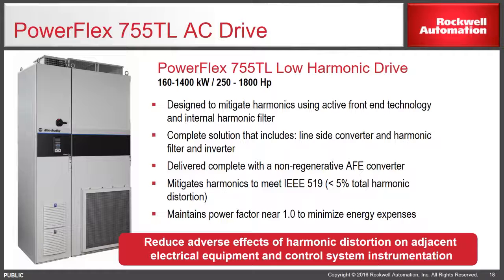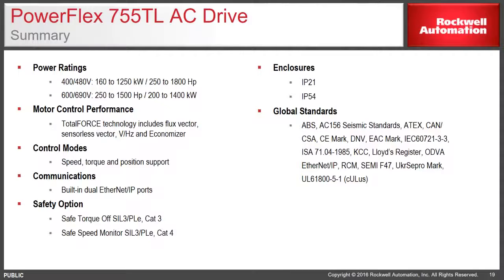The PowerFlex 755TL is available at 480 volt from 250 to 1800 horsepower, or at 690 volt, 250 to 1500 horsepower. The motor control performance uses total force technology, including flux vector, sensorless vector, volts per hertz, and economizer modes. It can control speed, torque, or position. It has built-in dual Ethernet IP ports. It has safety options of safe torque off, safe speed, both hardwired or network. The enclosures are NEMA 1 or NEMA 12. It meets all the global standards listed on this page.